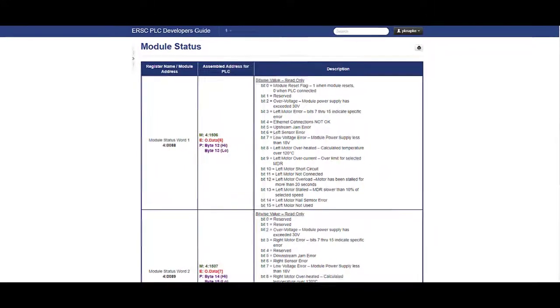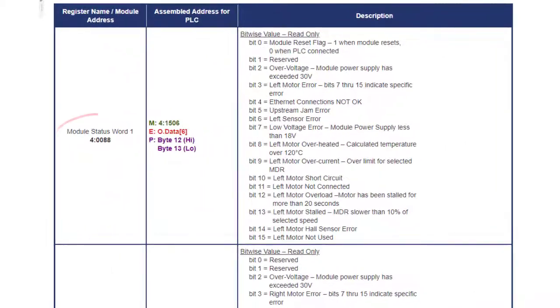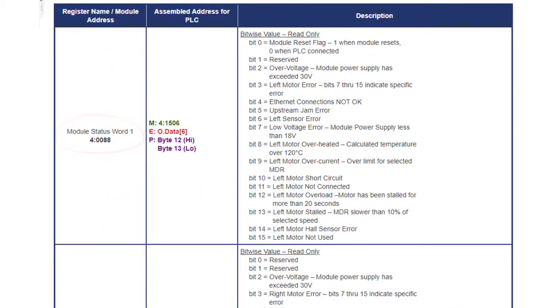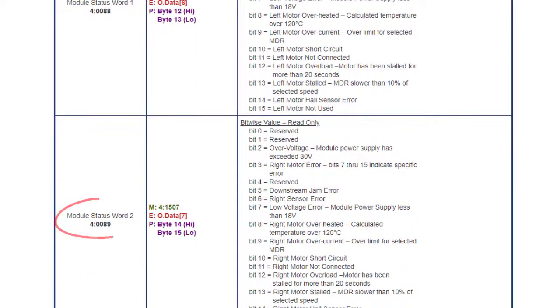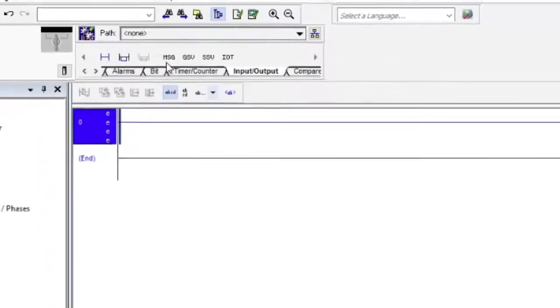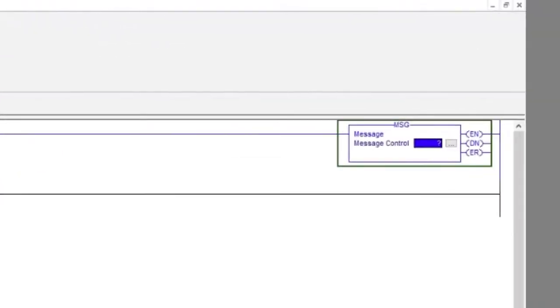What we want to do here is read the module's diagnostic data from registers 40088 and 40089 and put that data into a single double integer controller tag. Place the message instruction on a rung and enter a name for the controller tag that will control this instruction. For example, we are calling it read status.